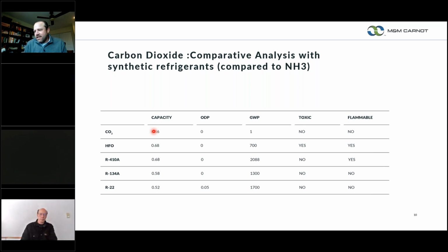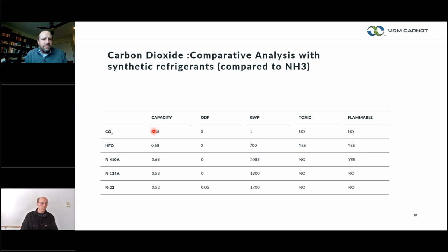And a large telecom provider up in Canada came and said, I have R22 cooling systems for all of my data centers scattered throughout Canada, and they're going to be end of life soon. So I'd like to come up with a solution where I can replace all of this R22 equipment with a natural refrigerant like CO2. So we formed a partnership, developed a prototype and a design, and tested it. We basically did everything to that machine that we could think of to see it work and to try to get it to fail.